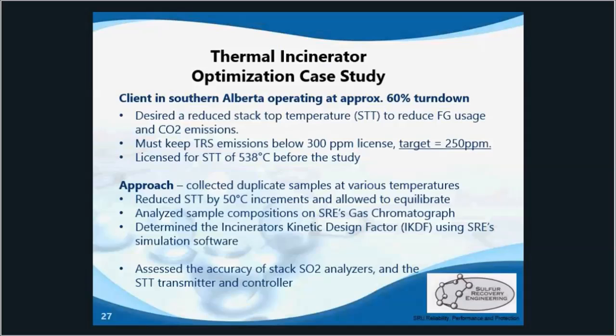So now we'll go over a case study for one of our recent incinerator optimization projects. This was a client in southern Alberta. They brought us in to optimize their incinerator at their new 60% turndown operation — a pretty big turndown. They were licensed for a total reduced sulfur emission limit of 300 ppm, so we chose a target of 250 ppm for a safe margin.